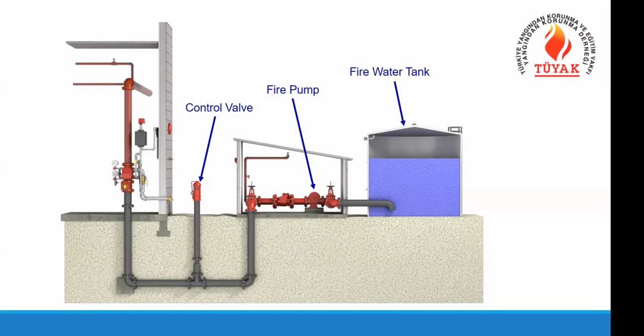So these are all defined in the local fire codes, and we have had the fire regulation in Turkey since 2002. In the main fire regulation we have different types of calculations to define the minimum quantity of the water tank. There are also some tables you can access online free of charge. So you can check this table. It gives you minimum tank sizes for different types of buildings and different types of risks. I also have details on how to calculate them.